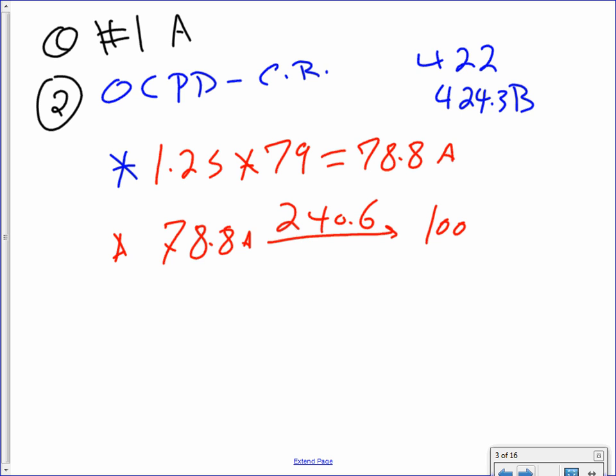I was gonna say, well, I must have to multiply a number by increase it 25% and come up with a lower number. You invented new math. That's right. Thank you. 78.8 amps. That's why I told you guys keep me awake. 78.8 amps. Right? And then this will get you 100 amp circuit breaker.